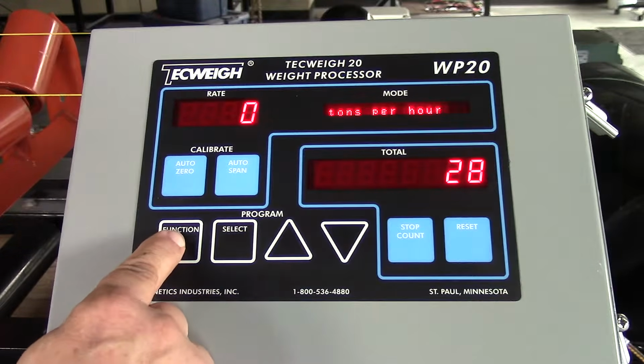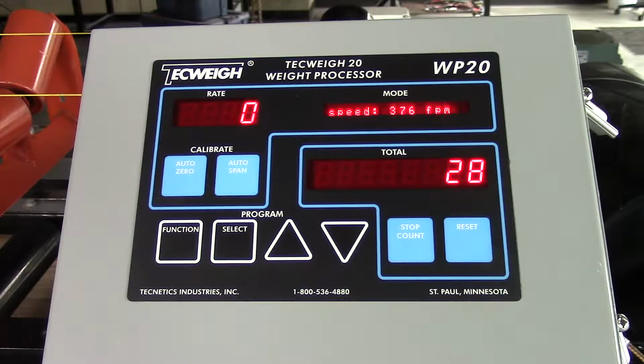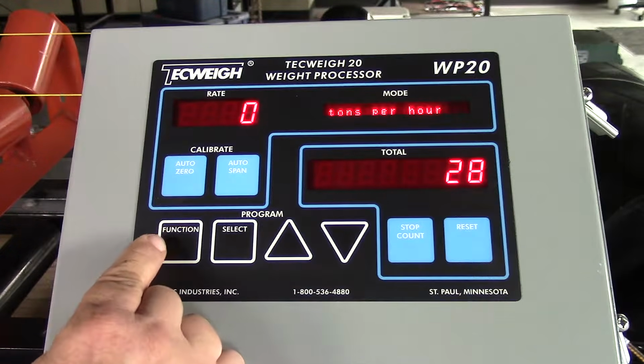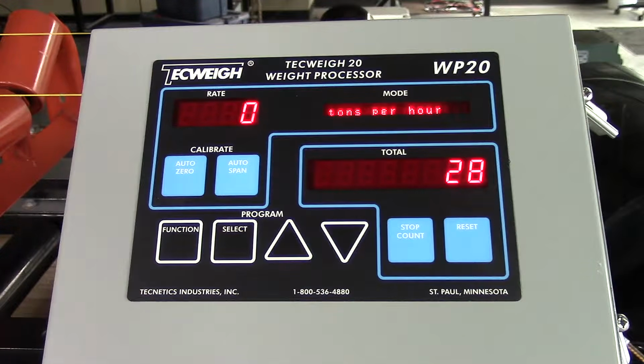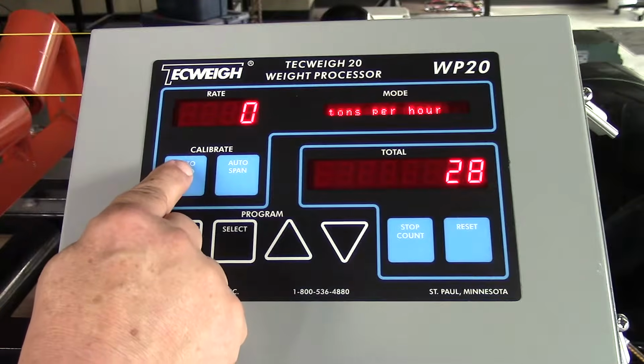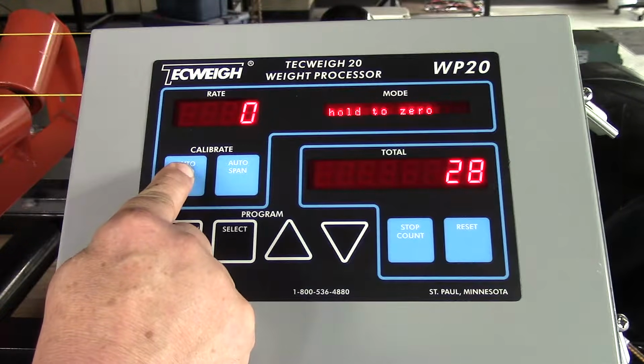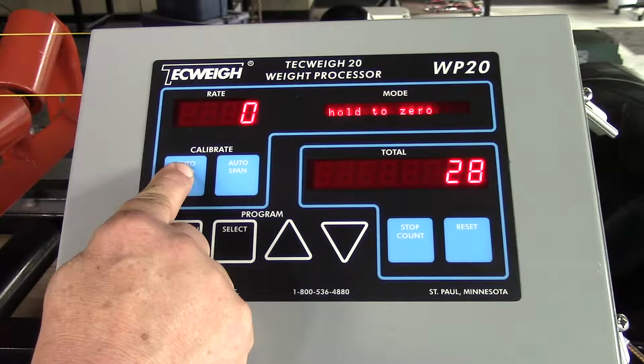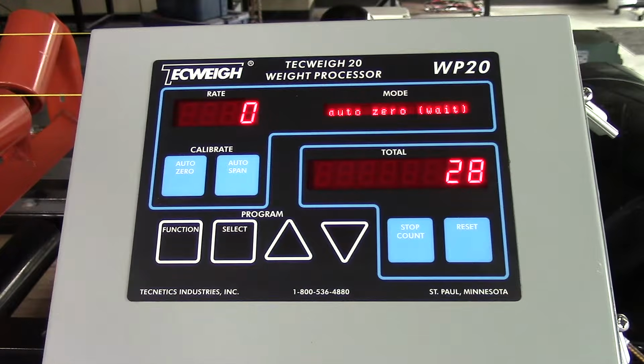Now let's begin with some simple calibrations. I'm going to touch the function key in this case just to make sure the belt's running. We have belt speed. In this case it's 376 feet per minute. Let the belt run empty for 10 minutes. If it's a newly started up belt, if it's been running for a bit, just make sure it's empty and touch auto zero. Hold it down for 5 seconds and the zero will start automatically.